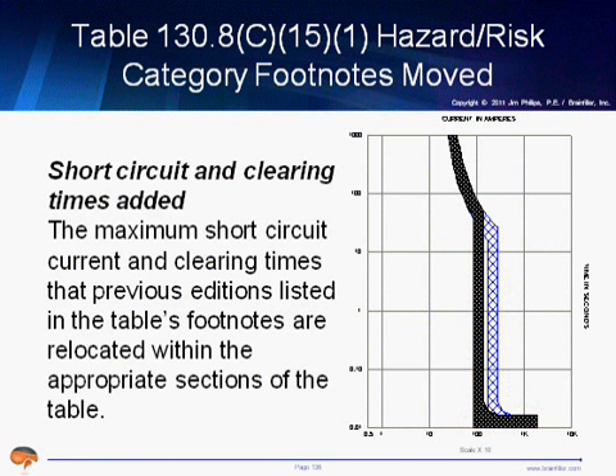And the magnitude of short circuit current and the protective device has a lot to do with the incident energy that you can have. And this is why these footnotes are so important. For example, I have a little red line out towards the right, a really high magnitude short circuit current. Well, the setting isn't going to matter as much. Whether you have a low setting or a high setting on the left, that's a time scale. This protective device should trip incredibly fast. But the problem is if you have a lower magnitude short circuit current, well, then the device setting is going to matter. If you have, for example, the higher setting, and you have a short circuit where I show the vertical red line, the short circuit current misses the trip characteristic of the higher setting. And in theory, this device could time out a very long time. Now, would it really time out that long?